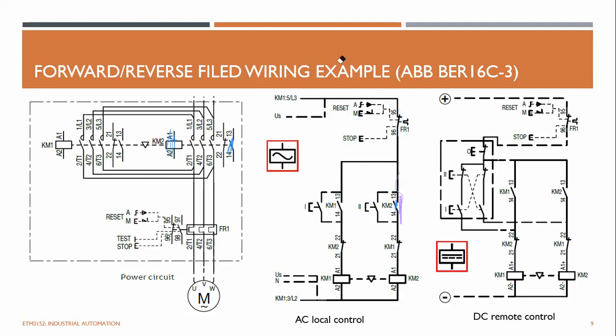Now the current is flowing from this path through the self-latch contact through here and going back there, and so this is closed and allowing the motor to operate in one direction. Interestingly, you can see these two are mechanically interlocked. This is a symbol of mechanical interlock.